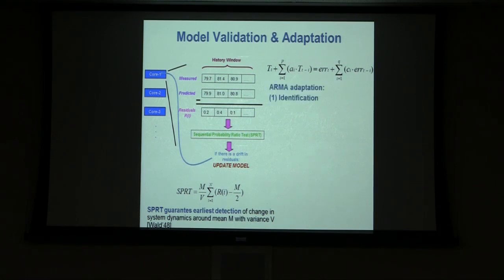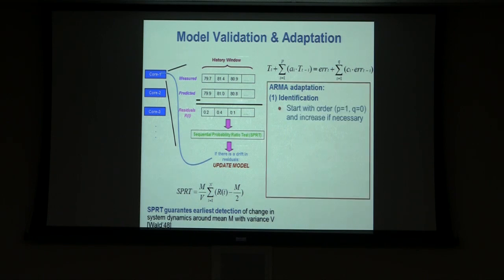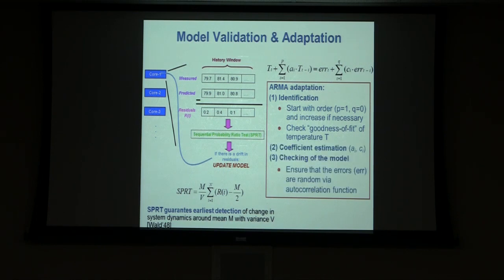For adaptation, we first go through a step of identifying which ARMA model we should use -- these are the P and Q parameters shown. You start from the lowest model and go up. In practice, it doesn't take a very high level model for most of this temperature behavior. It is higher level than simple exponential, because exponential doesn't catch these corner cases of a lot of on and off. Then, after coefficient estimation, we check the model again to ensure we got within reasonable tolerance.